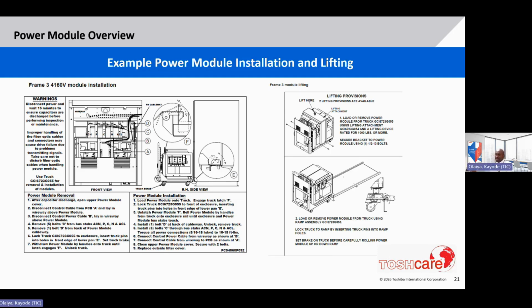You remember power modules rack in and out for maintenance. And the beauty of the Toshiba medium voltage drive is that the power modules can be racked out by the customer technicians. It is not necessary to have a Toshiba field engineer go to site to pull out the modules, though some customers still prefer that.